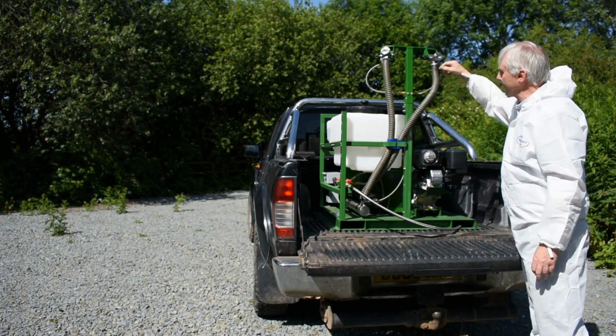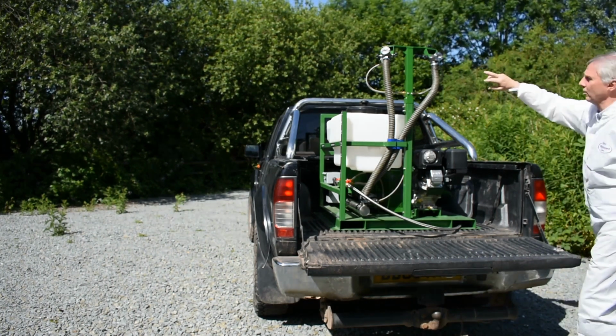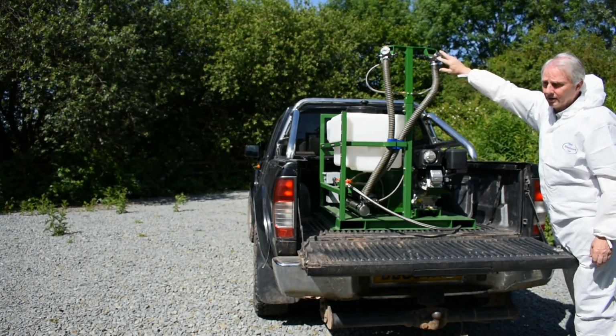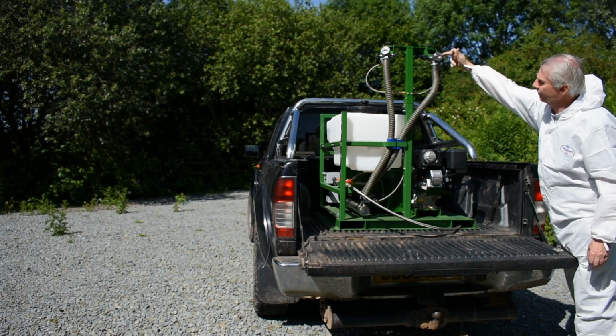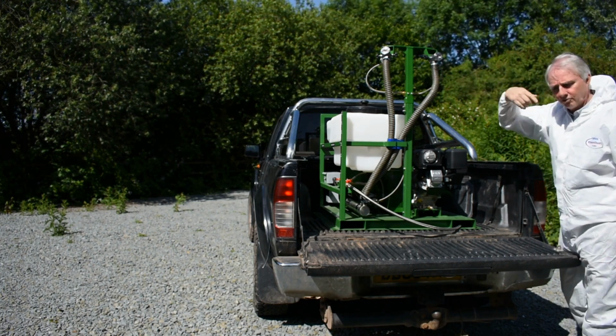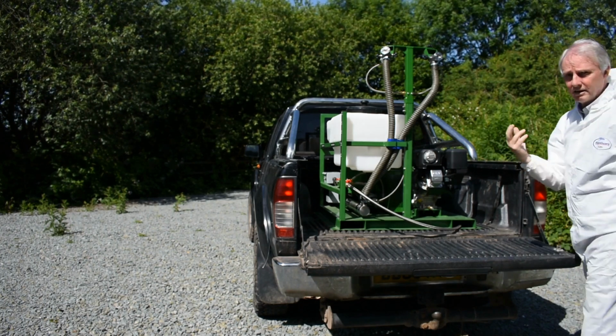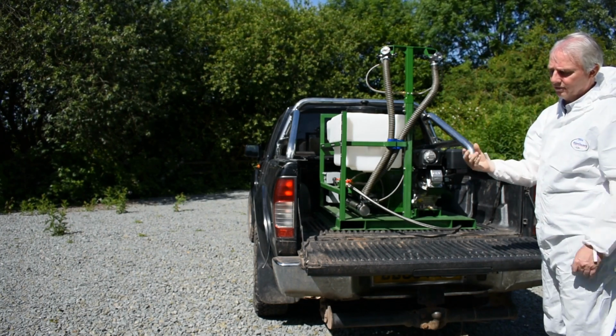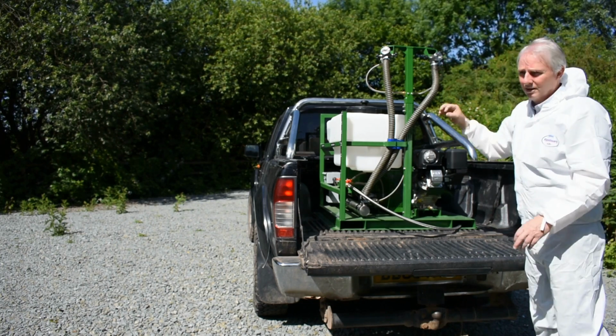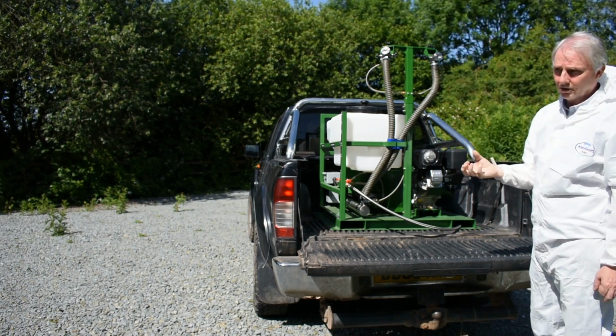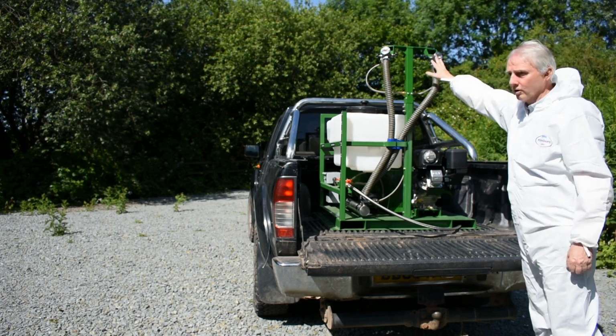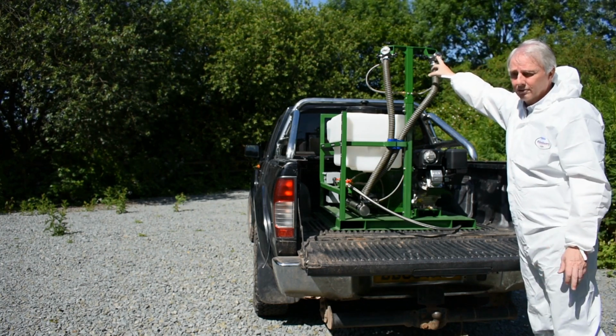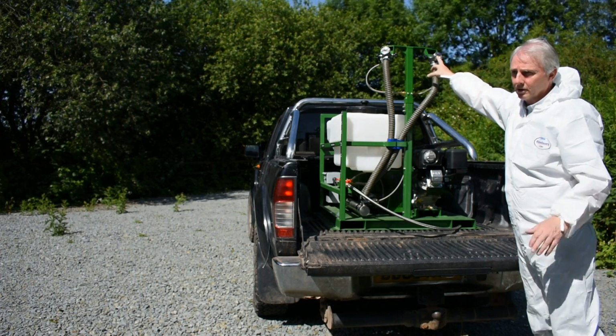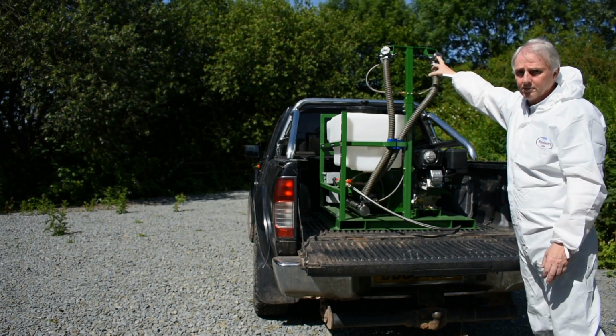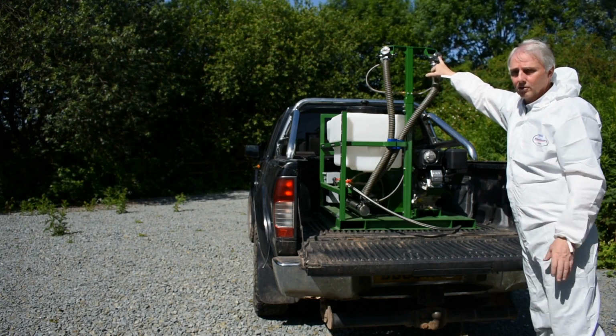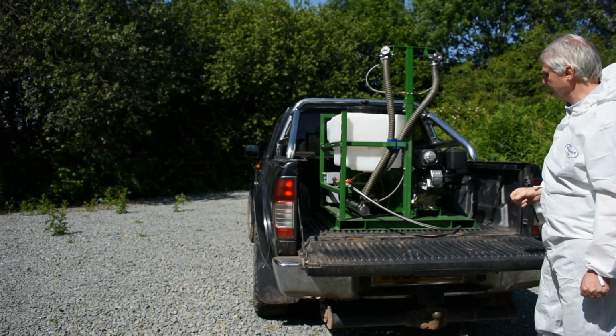The heads themselves are stainless steel, and we've got the nozzle. There's no rotating parts, no moving parts, so we're using a vertical nozzle, spinning the air to create the shearing effect for the liquid. A special designer nozzle will give us very precise droplet size control, which is a fog. Basically we're looking at particle sizes. With a water-based spray we're going to look at about 20 micron, with an oil-based about 15 microns. So it's a very fine fog, as we'll see when we fire the machine up.